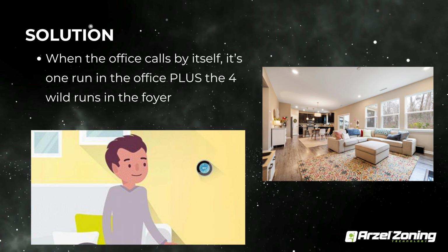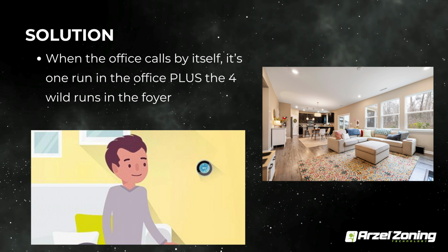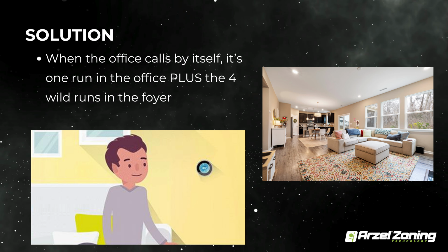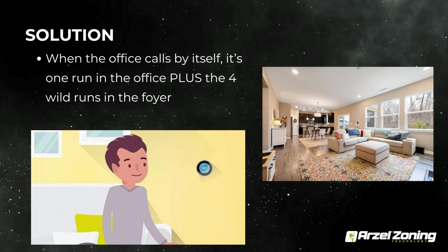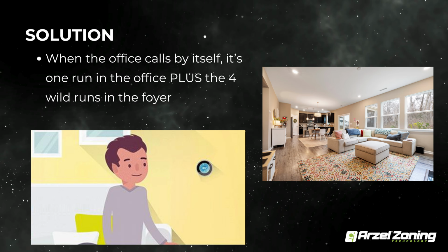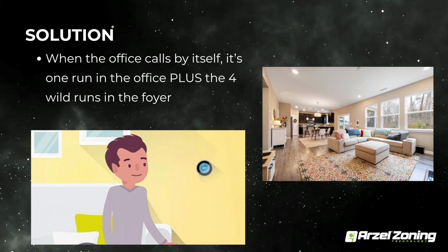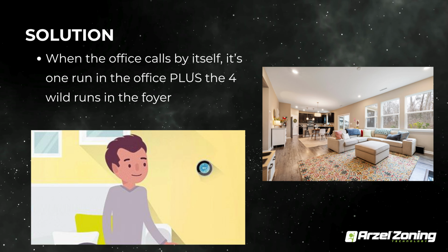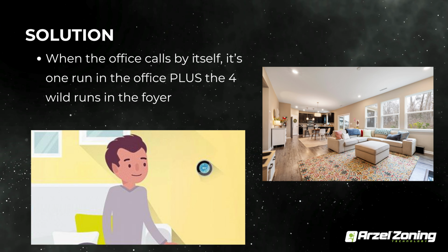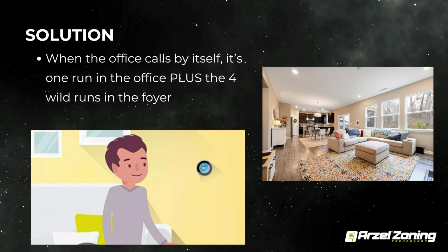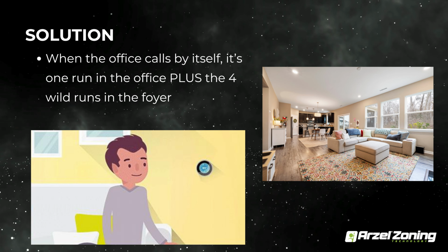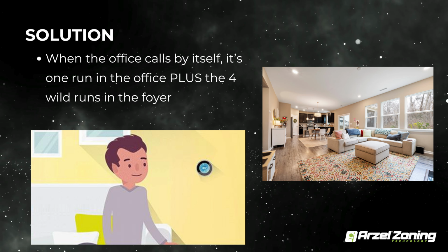But if I made this room an alone zone, one of these smart zone boards, and this thermostat called, and nothing was happening with the rest of the zoning system, we would all sit here and sweat or freeze or whatever the case is, because this cannot turn on the equipment. So, some different applications there.